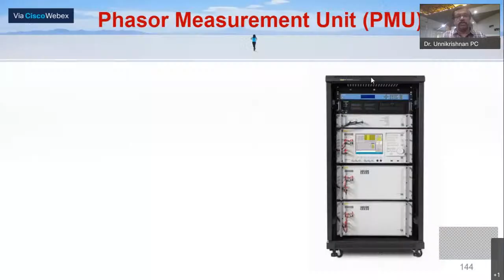So what is a phasor measurement unit? PMUs are digital data recording devices that measure and export GPS synchronized data. That is the most important thing. A PMU in one part of the country will be synchronized with another PMU in another part of the country. It means both of them have a common reference signal. That is very important. Only once you have the common reference signal can you find the phase difference. That is very important in electrical engineering. And their sampling rate is quite high, 6 to 48 samples per cycle. So you can have dynamic measurements of phase voltages, phase angles, currents, frequency, etc.